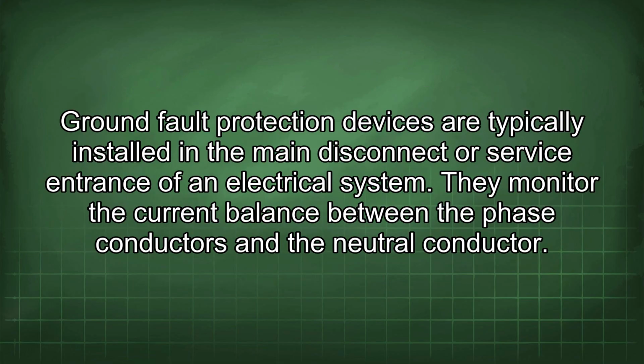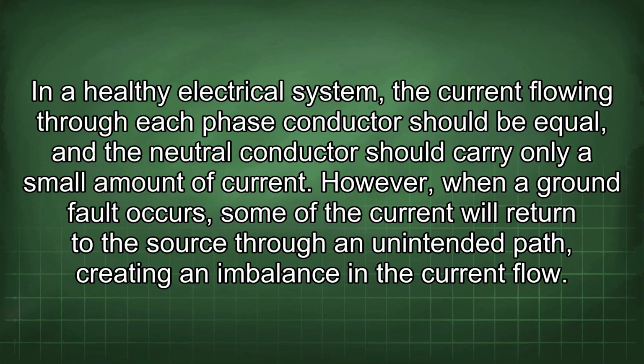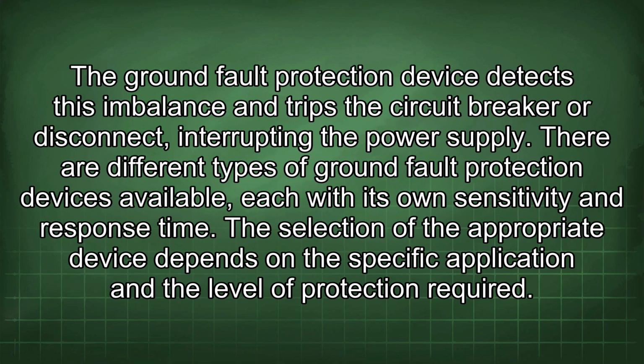Ground fault protection devices are typically installed in the main disconnect or service entrance of an electrical system. They monitor the current balance between the phase conductors and the neutral conductor. In a healthy electrical system, the current flowing through each phase conductor should be equal, and the neutral conductor should carry only a small amount of current. However, when a ground fault occurs, some of the current will return to the source through an unintended path, creating an imbalance in the current flow. The ground fault protection device detects this imbalance and trips the circuit breaker or disconnect, interrupting the power supply.